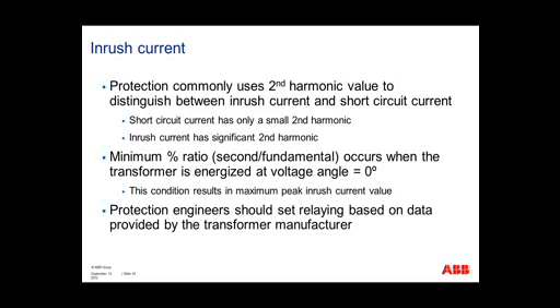So most protection schemes look at the second harmonics to distinguish between inrush current and short circuit current. The reason for this is the short circuit current has only a very small second harmonic component. However, the inrush current has a very significant second harmonic component. The minimum percent ratio, second over fundamental, occurs when the transformer is energized at angle 0. And we've seen that in the previous slide. This results in our peak inrush current that we need to account for. And protection engineers should set relays based on data from the transformer manufacturer.